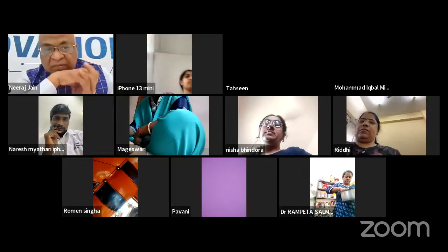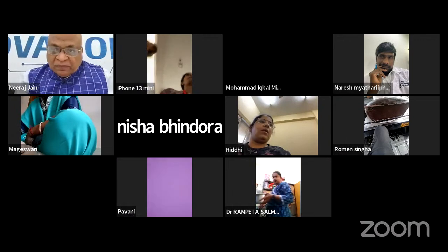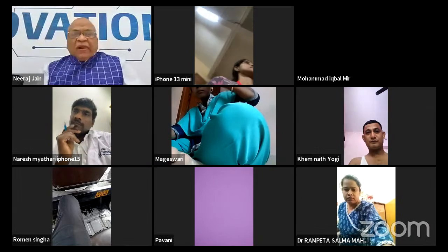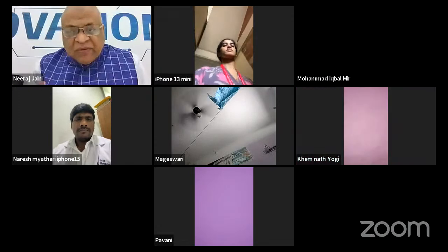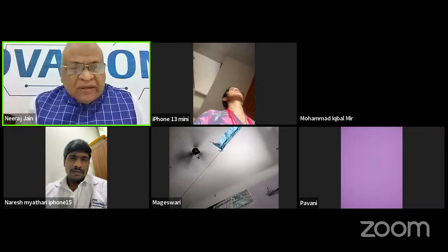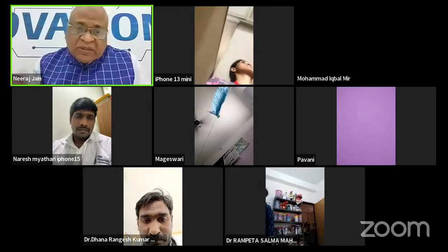First question: is it necessary to periodically check AMR or linearity of a test in clinical biochemistry, even if I use the same equipment and calibrator or reagent without any change? Yes, it is needed. The frequency required is once in 12 months. You can check linearity again. Why is it required? Because there is wear and tear in the equipment. Previously, whatever linearity it was providing you, there may be some change in the linearity. So once in 12 months, you test this linearity.